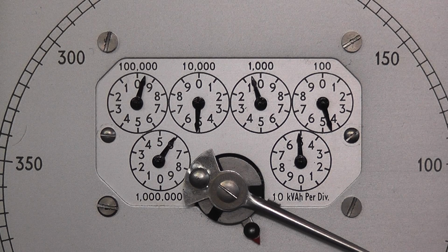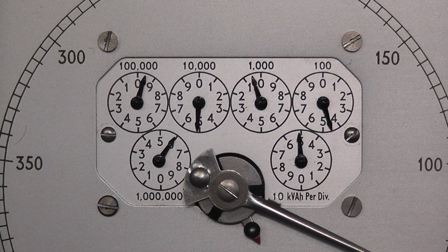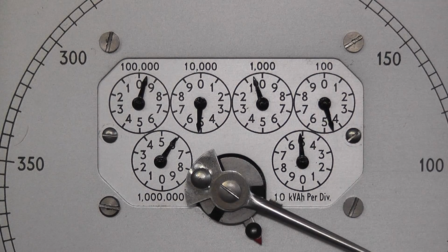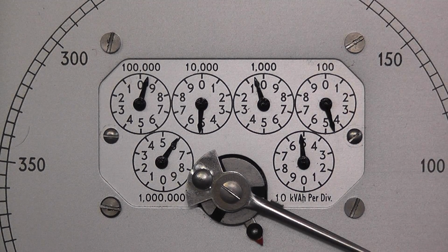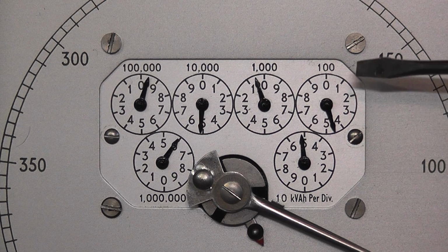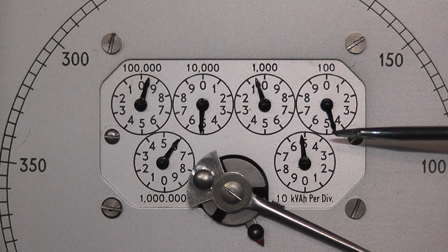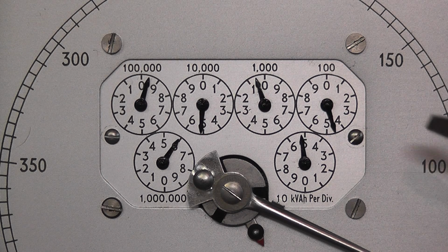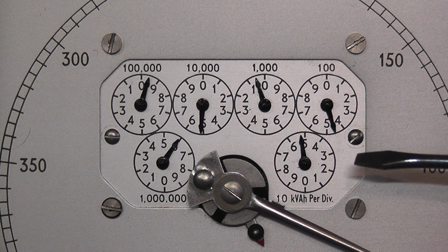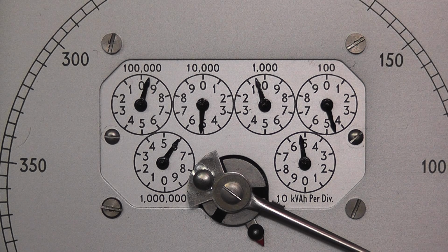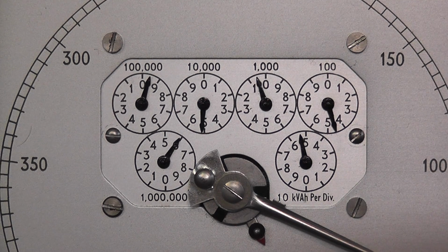Okay, another thing, have a look at the dials. To make life hard for meter readers and everybody, but it's still interesting. The bottom two registers are inversed as the opposite top registers. The 5 is on the top and the 5 is on the bottom. Besides the fact that one dial goes to the left, one goes to the right, one goes to the left and so on. These are mirror images, so the lowest denomination factor is times 10, 100, 1000, 10,000, 100,000 and 1 million. So this particular meter reads 5,950,453 units, kVAh.